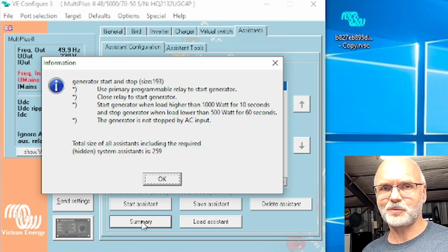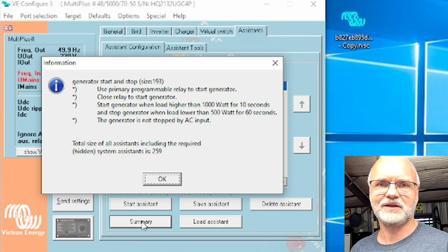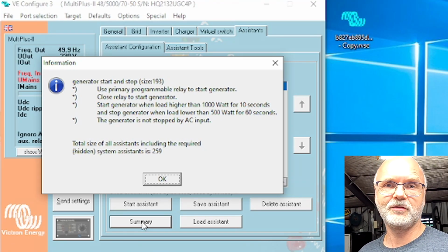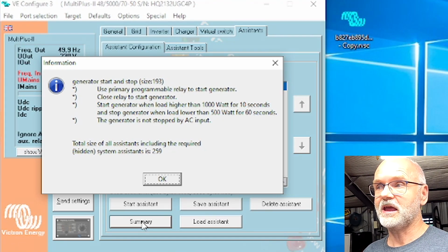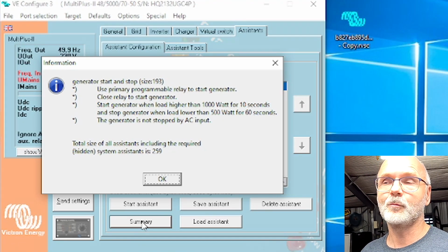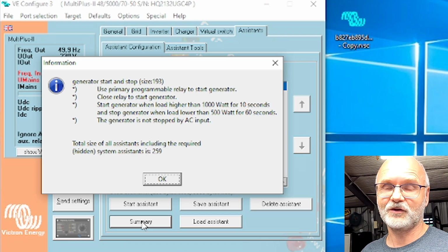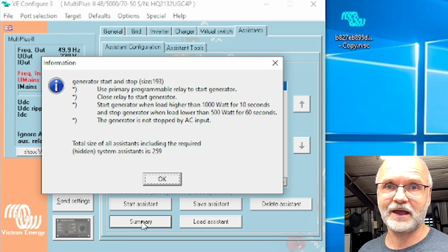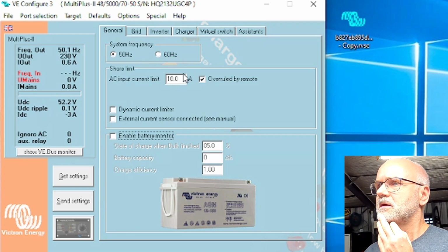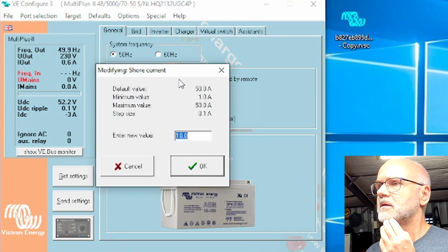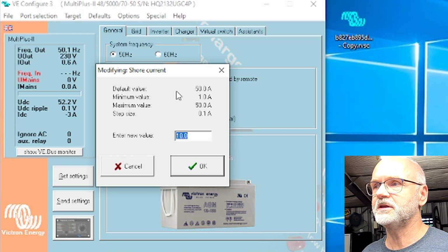For test purposes I have now changed the parameters in the Assistant to turn the Phoenix inverter on if we have a load of more than 1000 watts for 10 seconds, and turn it off again if we go below 500 watts. Also I want to set this one here to 1 amp.